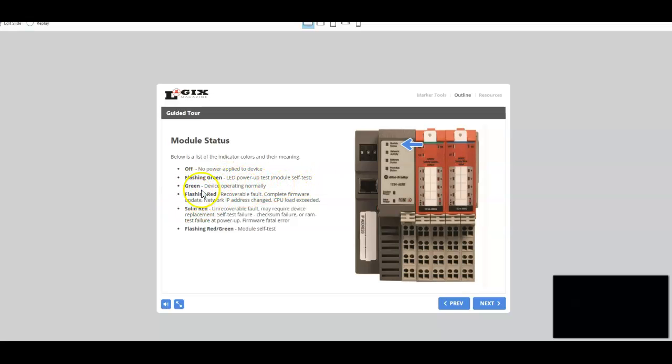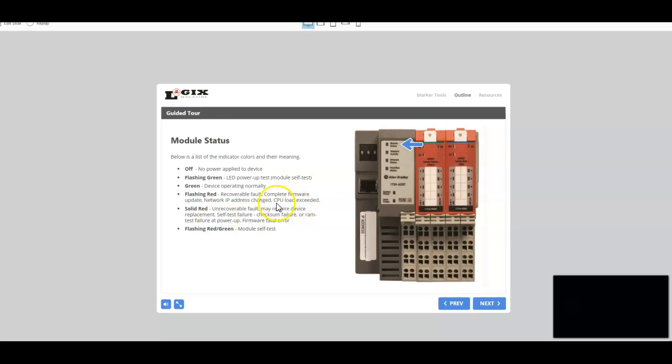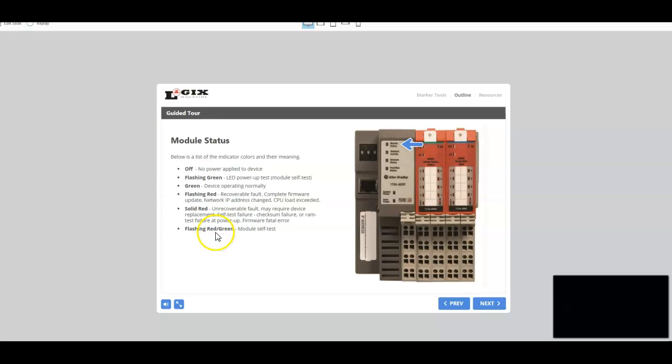If it's solid green, devices are operating normally. A flashing red means there's a recoverable fault. A solid red is an unrecoverable fault. And we identify things that you should do and look at if any of these lights or these indicators show these conditions.